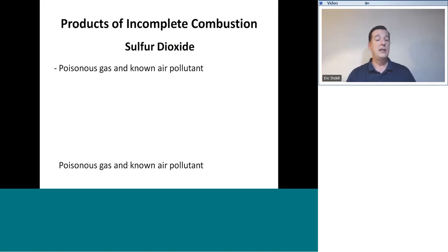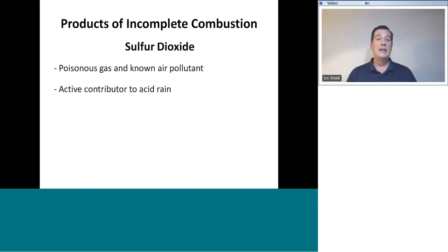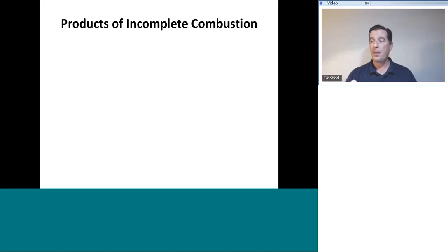Sulfur dioxide can also be produced. This is a poisonous gas and known air pollutant. It's an active contributor to acid rain. Now, the actual production of sulfur dioxide from a natural gas flame is very, very low. Sulfur dioxide is more commonly associated with coal fires than natural gas fires. However, sulfur dioxide can and will be produced in a very poorly burning natural gas flame that has a very poor fuel and air mixture. So just something to be aware of.